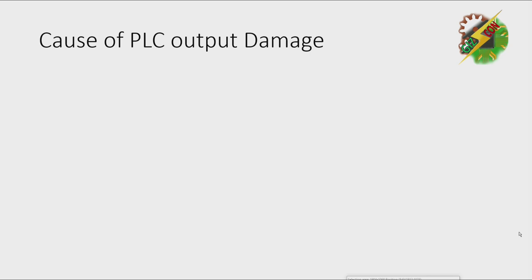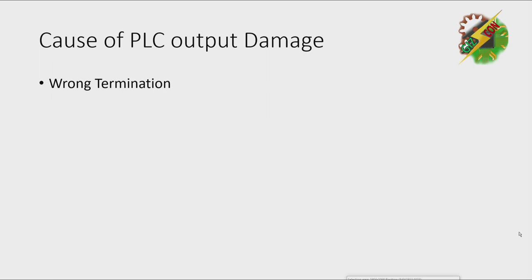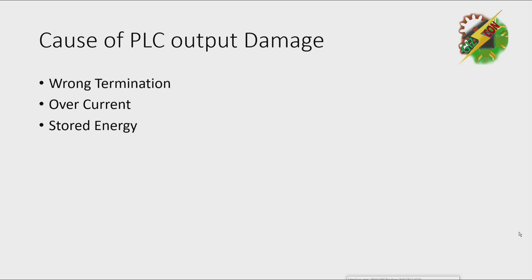First of all, we need to identify what are the causes of PLC output damage. First, wrong termination. Second, overcurrent. And third, stored energy.